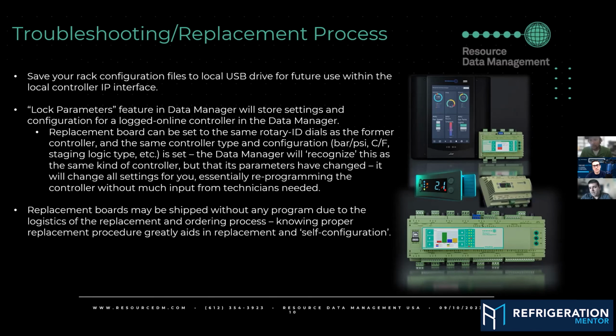And if you have locked parameters, all the parameters in the data manager, you can save them and lock them in place. The data manager will see that new controller that might not be programmed at all, and it will go, oh, hey, I recognize this controller. You're the controller that's been offline for a while. Where you been? And then it will dump those settings back into the controller because it'll go, hey, my settings have changed. So you don't have to necessarily worry about programming. It can self-program itself, but it is reliant on certain things like that rotary ID identification. If you were to set that to something else entirely, the data manager wouldn't recognize it as that controller. It just recognizes it as a controller.